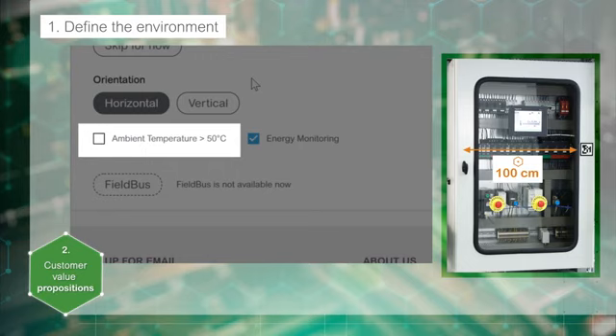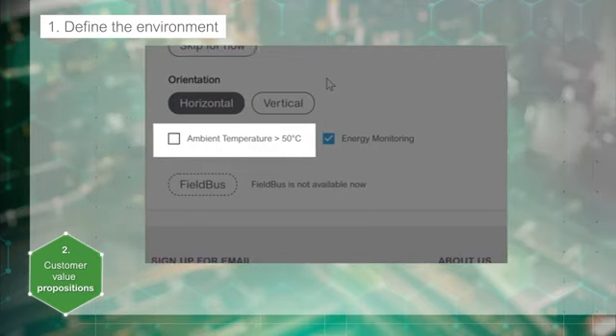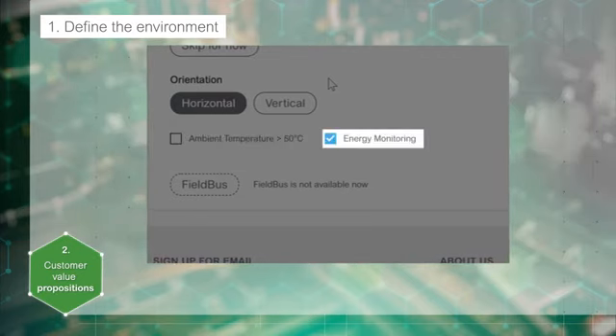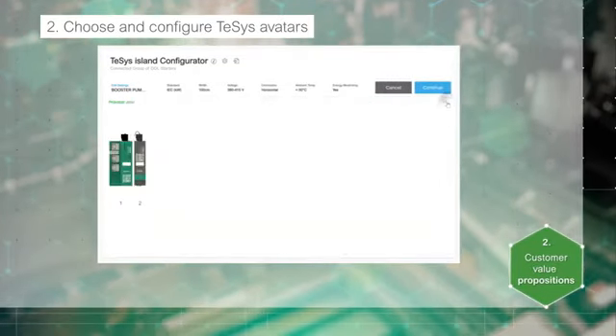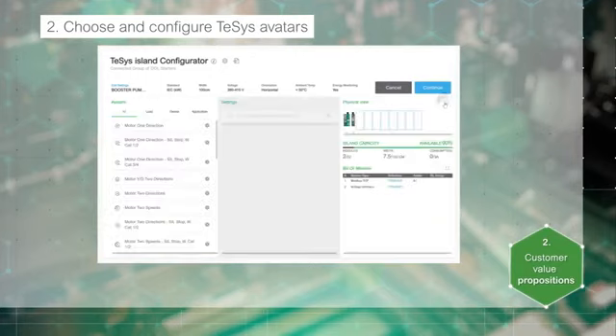Derating is automatically calculated when ambient temperature above 50 degrees Celsius and/or vertical orientation are selected. At this step you also decide whether you need energy monitoring, to get information on energy consumption at the load level. The bus coupler is then defined, and potentially the voltage interface module if energy monitoring is checked.